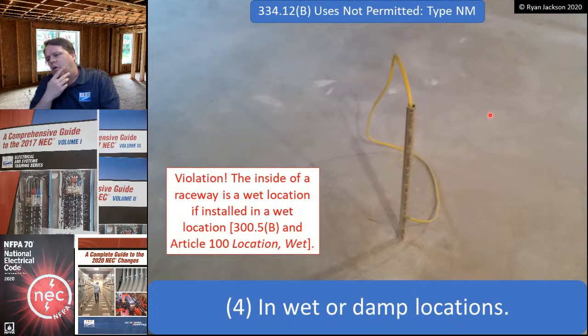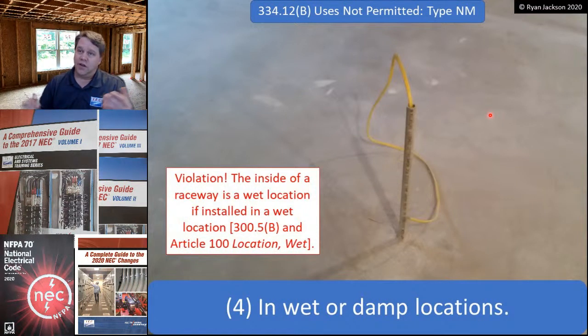This is a violation I wrote up dozens of times as an inspector. We're into basements where I live, so usually when you build a house, you have an unfinished basement. Later on, when somebody goes to finish the basement, they'll often want to have a kitchen down there with an island. And of course, 210.52(C) says if you have an island, you need receptacles in your island. So how do you get that wiring method out to the island in an unfinished basement? Well, you end up saw cutting the floor, and then you'll put a PVC conduit sleeve in the floor, and then you'll pour back over it.